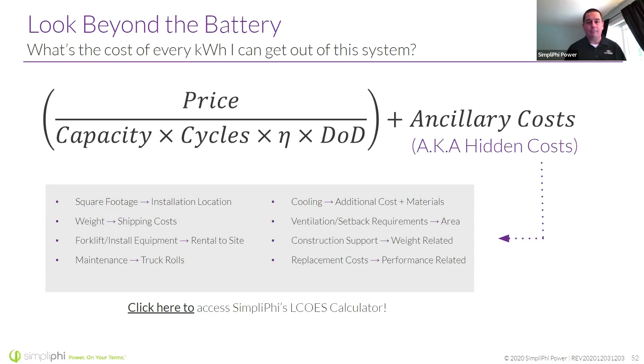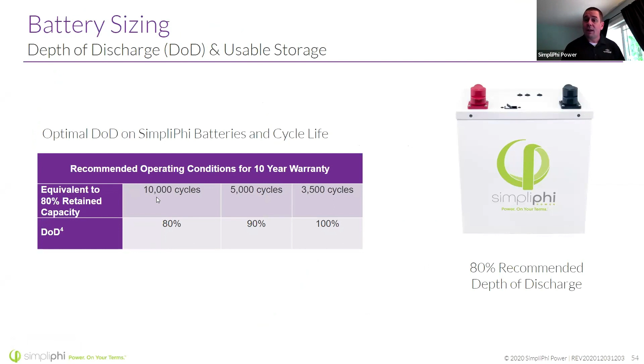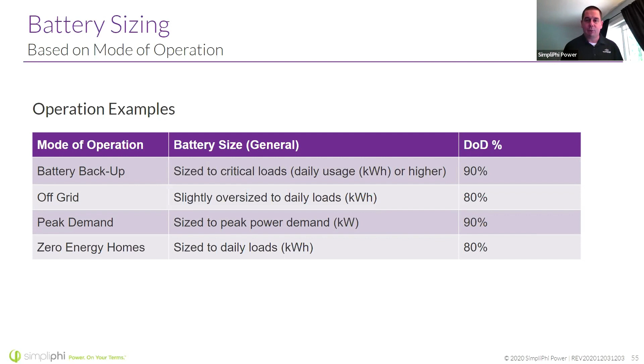Real quick on battery sizing, we talked about depth of discharge. We anticipate if you go to 80% depth of discharge, you're going to get 10,000 cycles out of our battery. You can do 100%, but you're really only going to get that 10-year warranty life, where 10,000 cycles pencils out to something more like 20 plus years. Depending on the application, you might say, hey, if I've got a battery backup system that's only going into backup maybe a dozen times a year, 90% is appropriate. But if you're off grid, or cycling to the grid daily, using that battery 100% or to 80% daily, we're going to say 80% is a good number, because you're going to get that maximum life and those additional years after warranty.